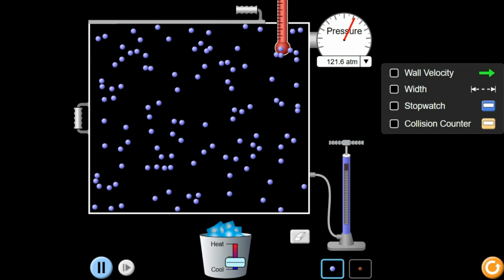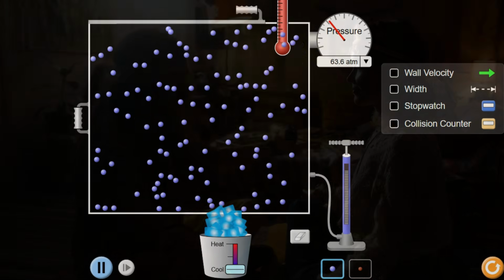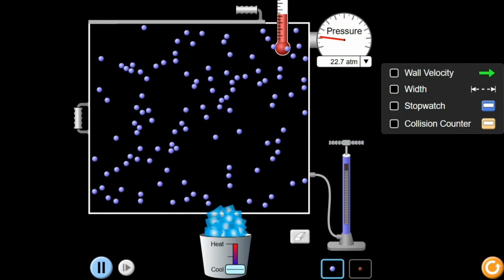When we remove heat from the refrigerant, the opposite happens. These particles start mellowing out, they get chill, maybe sing a little kumbaya, and we see the result of this activity by a drop in the pressure on our gauges. So the changes in pressure we're seeing on our gauges are signifying that we're either gaining heat or losing heat somewhere in the process from wherever we're measuring those pressures. And if we see abnormal pressures, high or low, that's telling us even more of that is happening in that location. So let's go back to our condensing unit where we created the problem.